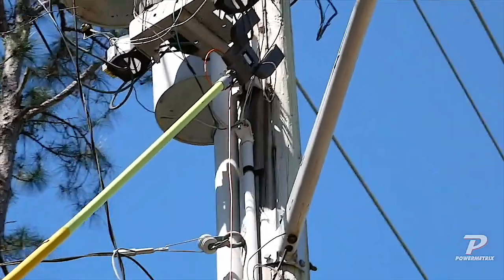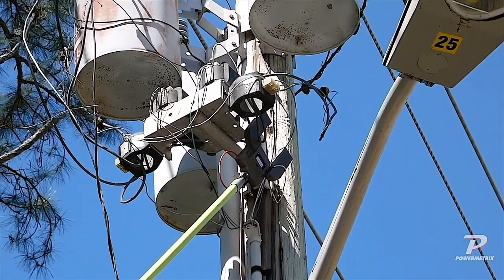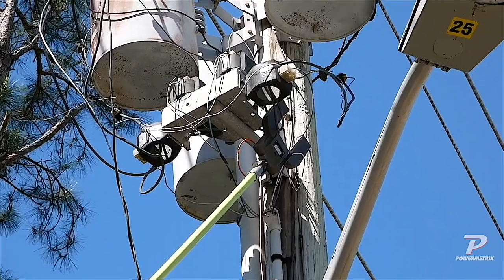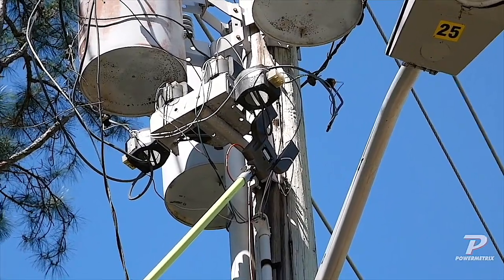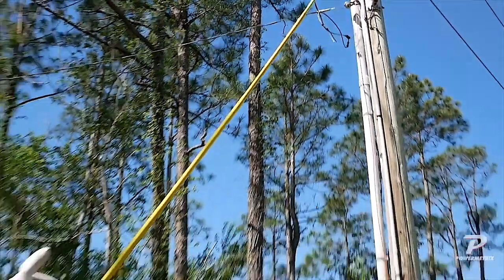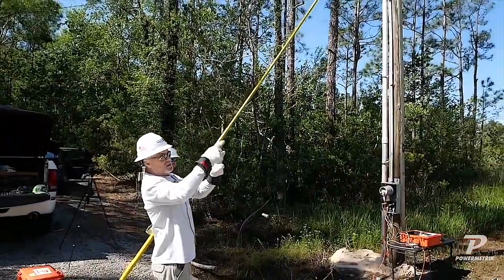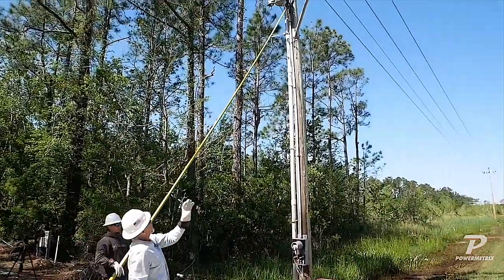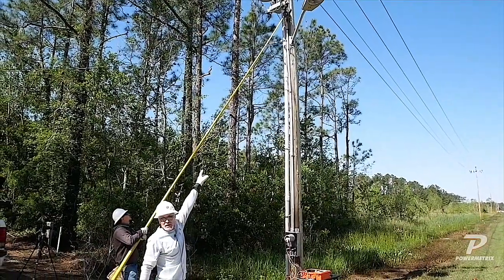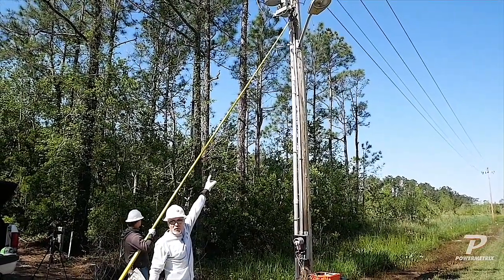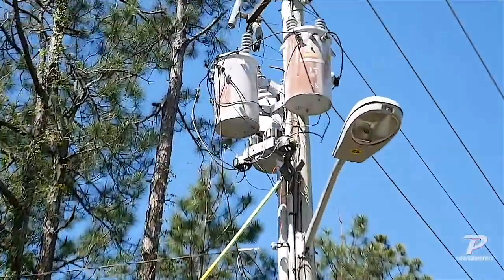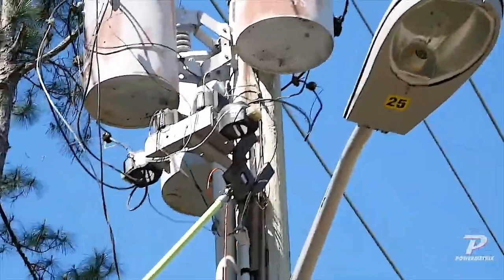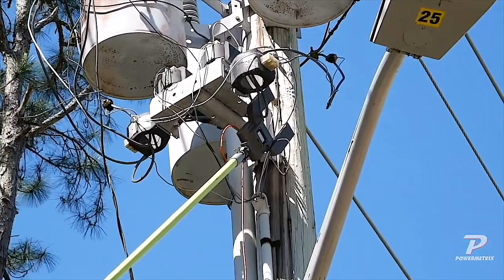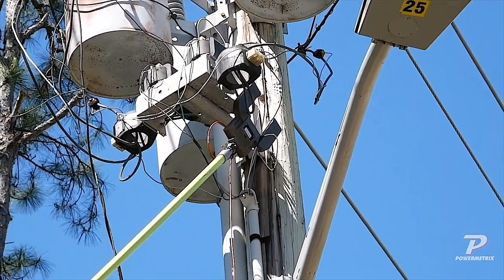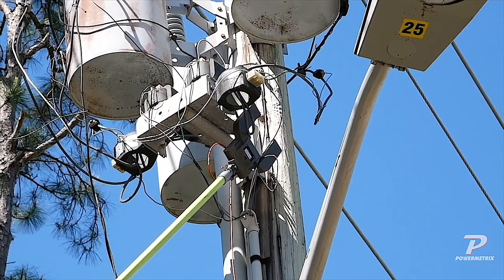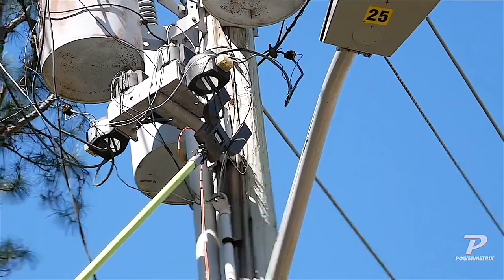This is just great stick work. He's got to get through that loop, right? Because remember, we're looped through on that 480, like we talked about when we inspected the pole. So he's got to get through that loop with the one fork. But you always have to be cognizant of all those secondary wires, instrumentation wires, and control wires up there. He's had to get in between all those, but he didn't get any of the others in there. It's similar to a flex up in a pad mount, you don't want to grab extra stuff. He's done a great job of just getting that loop in there and leaving all those other wires out. Let's go hit the button and see what happens.